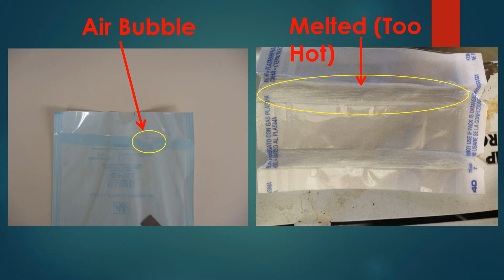And this is really the reason why. On the left here, you see an air bubble. That is a heat seal not done well, either with poor contact or not the right temperature. And on the right-hand side, we see one that is just entirely too high, and that is starting to melt the item. It could be that this was set for a regular peel pouch and they were attempting to do Tyvek. Your high temp and your low temp peel packs oftentimes are at different temperature settings.